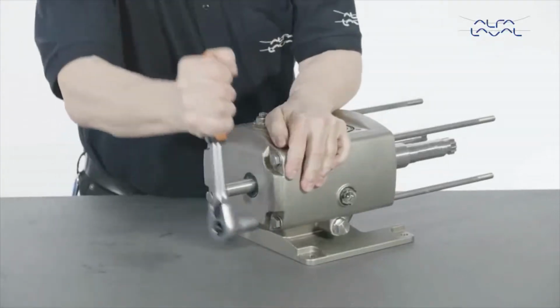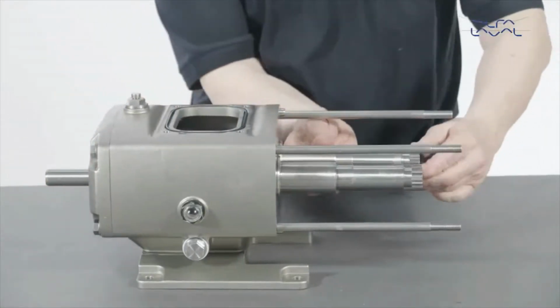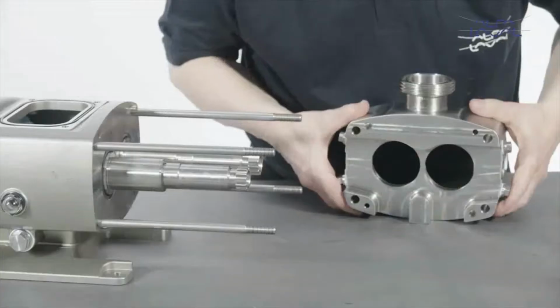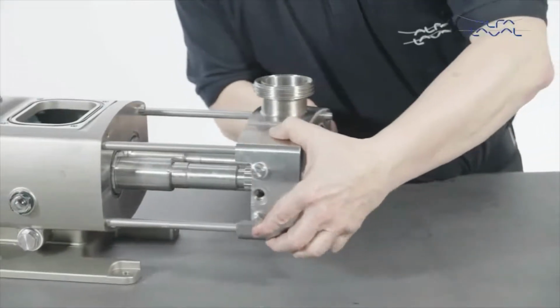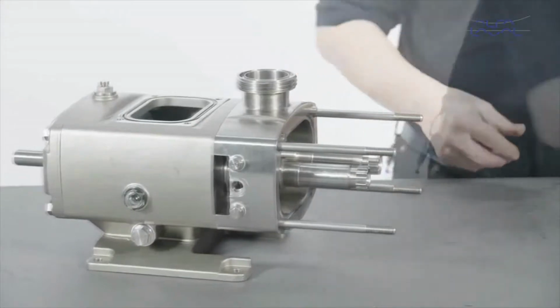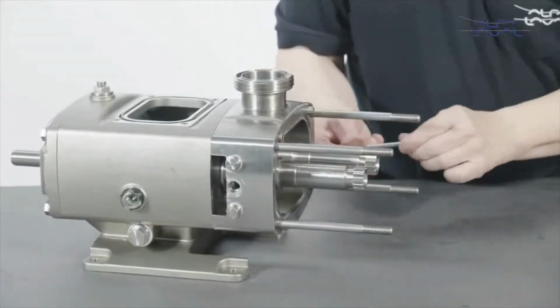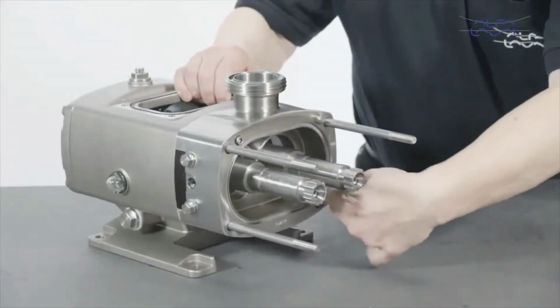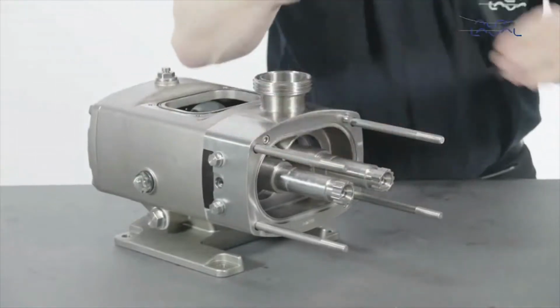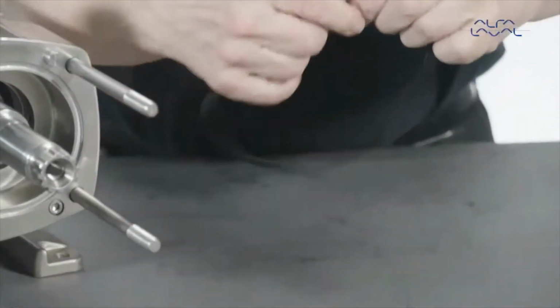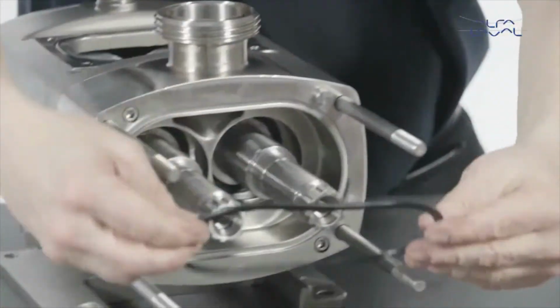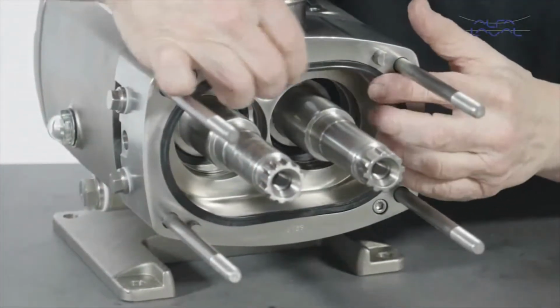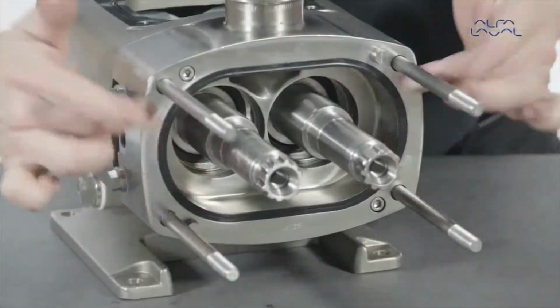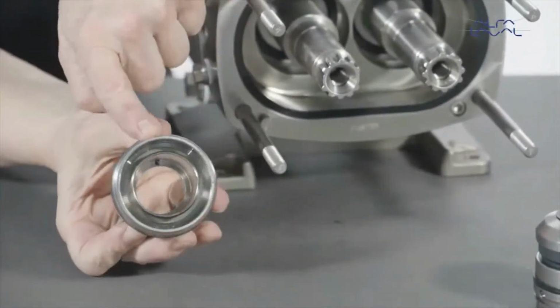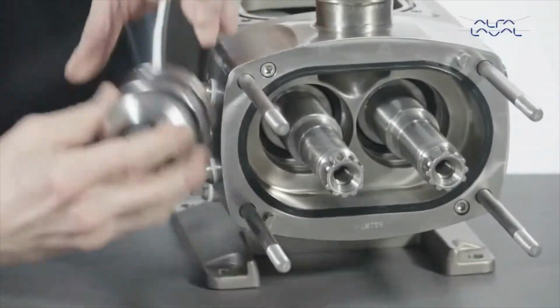Position the gearbox and bolts, then tighten. Make sure the gear rotates on the sleeve. Remount the seal housing and tighten the cap screws. Lubricate and replace the pump casing elastomer. Mount the cartridge seal onto the shafts. Notice the indication marks.